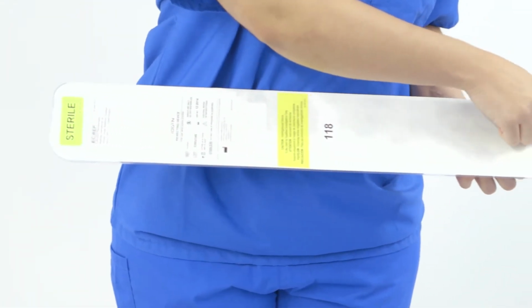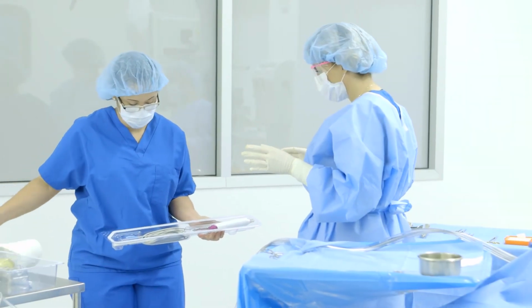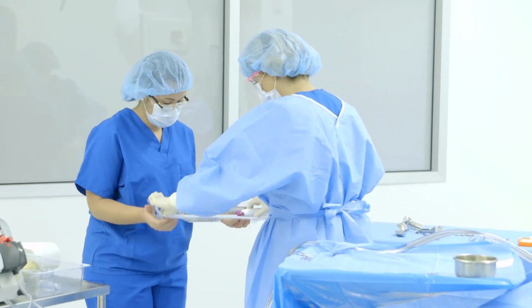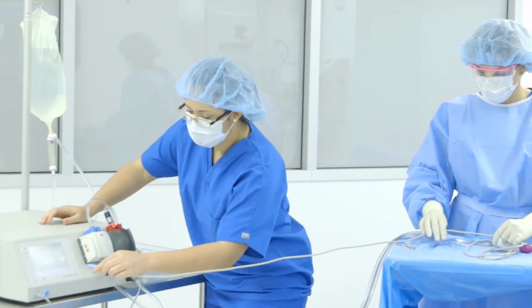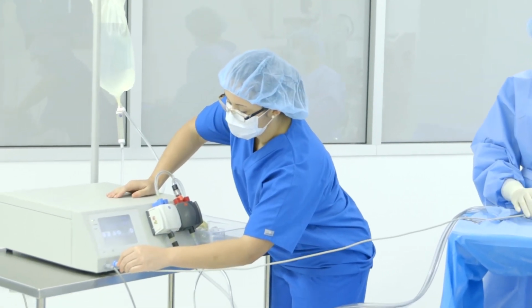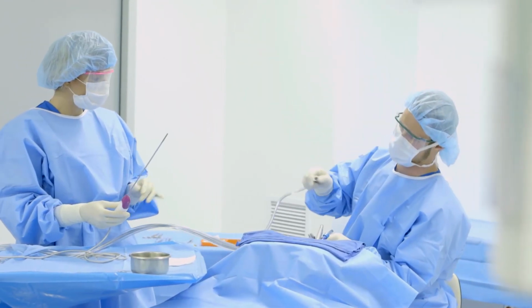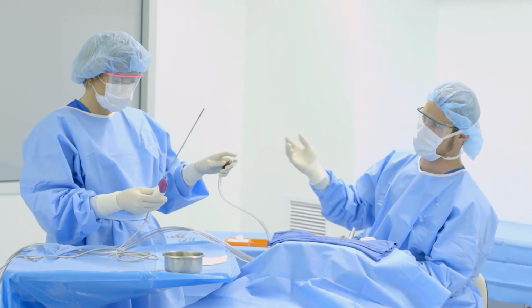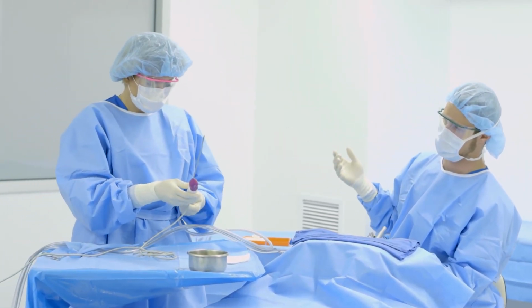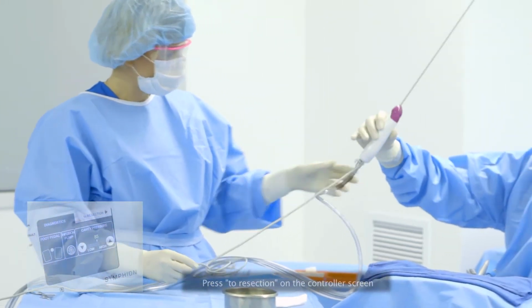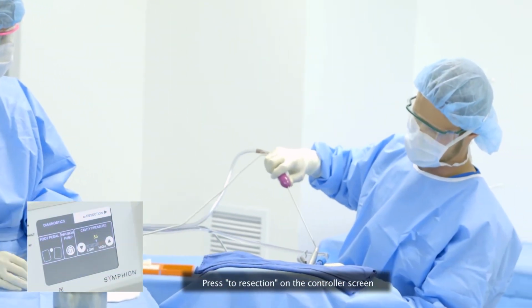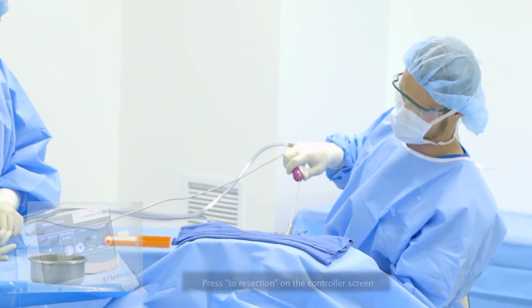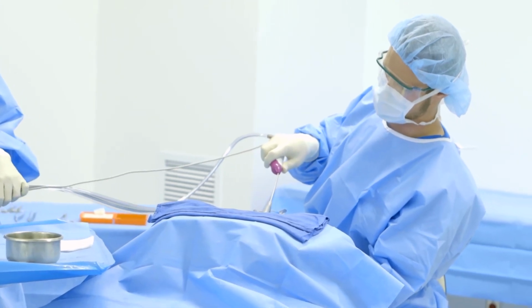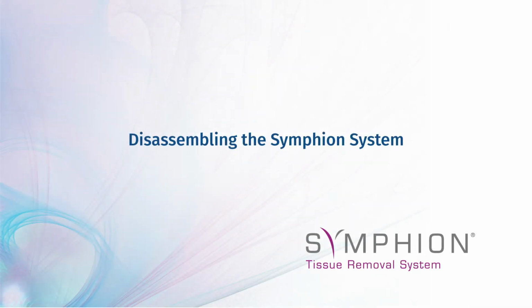Following sterile practice, remove the resecting device from the tray and place it on the sterile table. Connect it to the controller. Disconnect the aspiration tube from the scope and attach it to the resecting device. Insert it into the working channel of the endoscope. Press to resection on the controller screen. Follow standard operative hysteroscopy practices for resection.